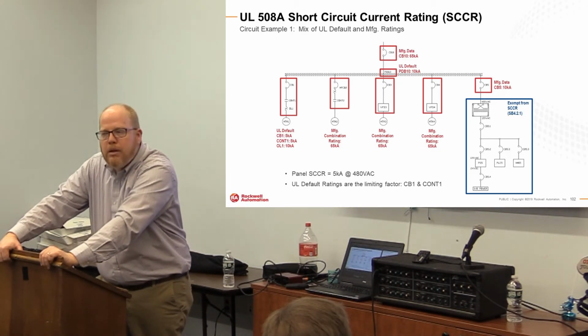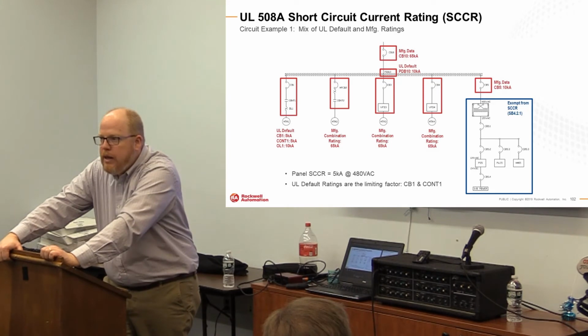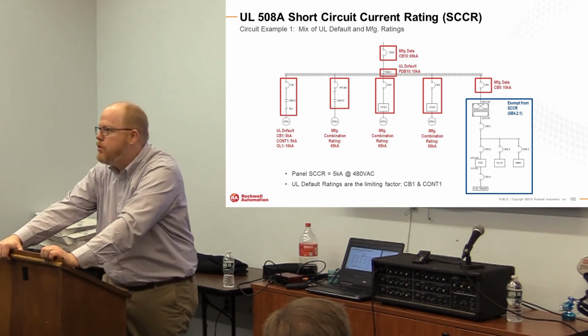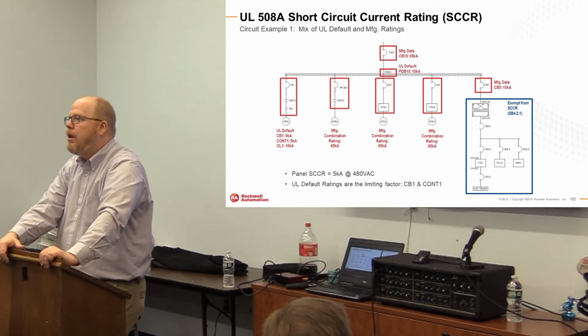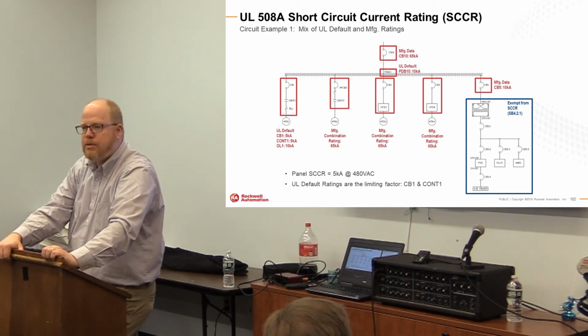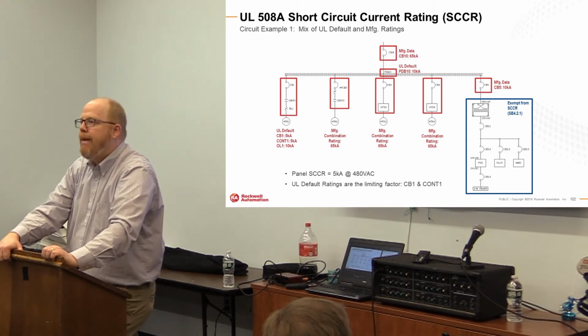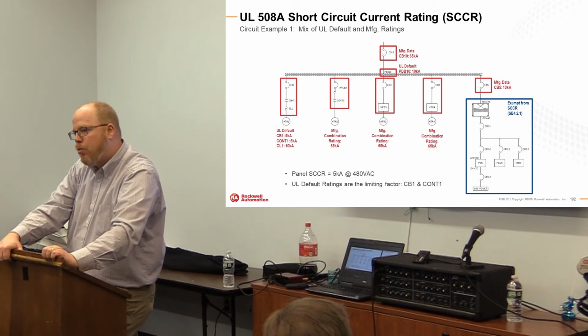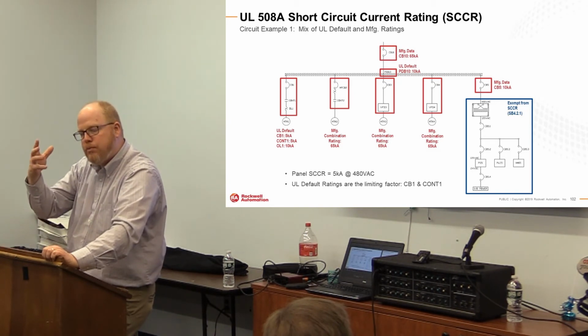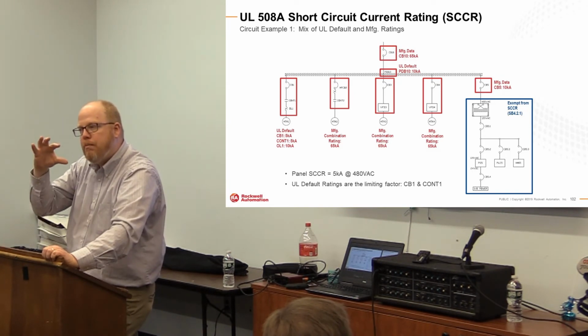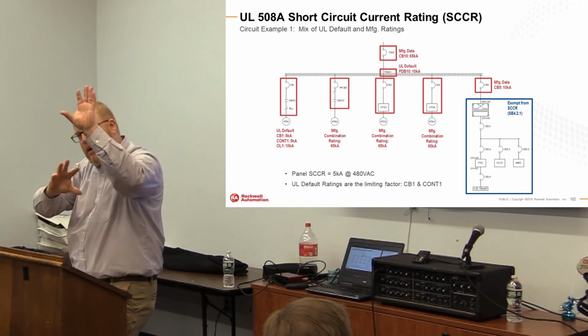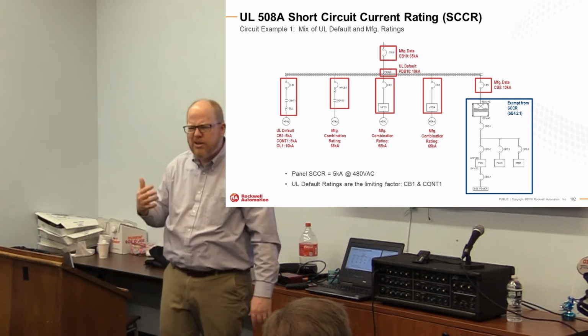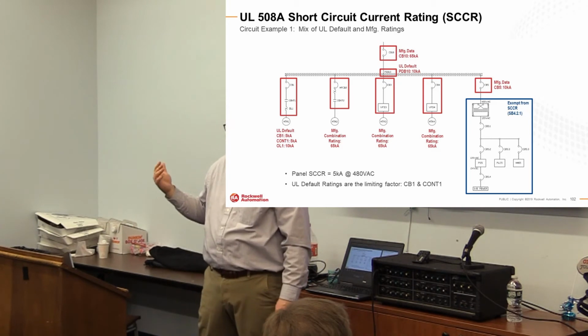Another very common pitfall is in the feeder, when you do power distribution in the feeder. Power distribution blocks sometimes will mess you up. There are two ways you can get around it. Number one is we list our circuit breakers and fuses and feeder power distribution blocks as a combo rating. Many of them are 65. With fuses, they're 100, sometimes 200.